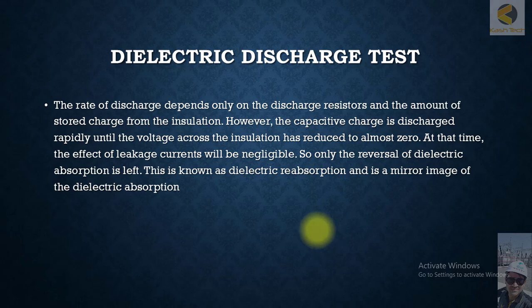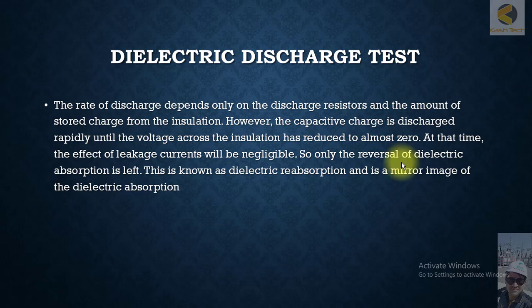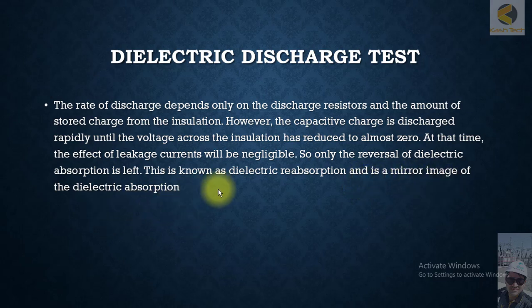Let's continue the topic of dielectric discharge test. The rate of discharge depends only on the discharge resistors and the amount of stored charge from insulation. The capacitive charge is discharged rapidly until the voltage across the insulation has reduced to almost zero. At that time, the effect of leakage current will be negligible, so only the reversal of dielectric absorption is left — this is known as dielectric reabsorption, and is a mirror image of dielectric absorption.